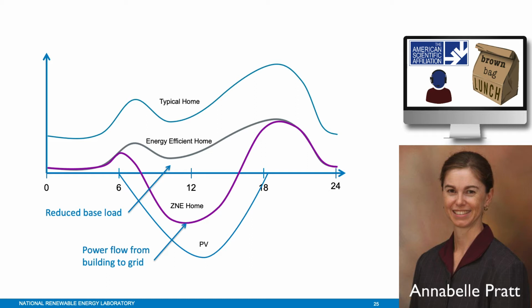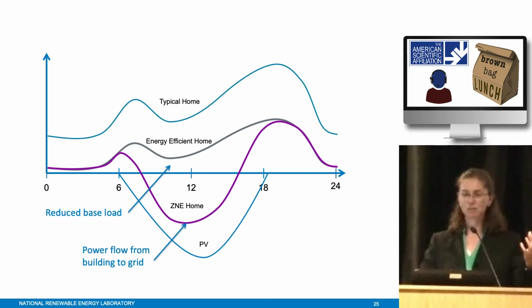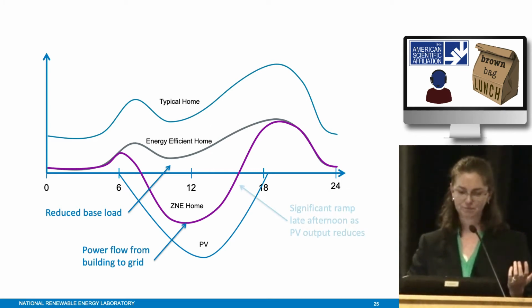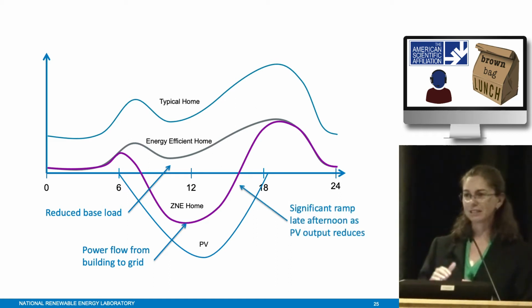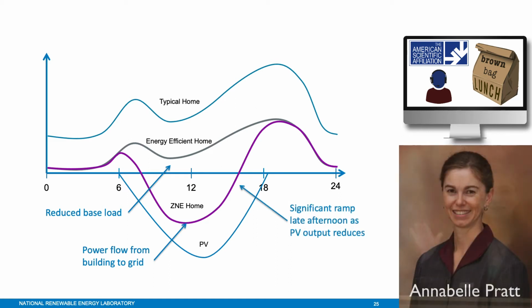Where we started earlier with power flow from left to right, from central generation station down to the load, that's what the grid was designed for. But now we're introducing a load that can produce power, and power flow goes the opposite direction. This introduces a significant ramp, because right as you hit your peak in the evening is also the time when you lose your PV generation. This makes it harder to get all of those generators online to match generation with load every second. This is sometimes referred to as the duck curve, the neck and head of the duck, and in Australia it's called the emu curve.